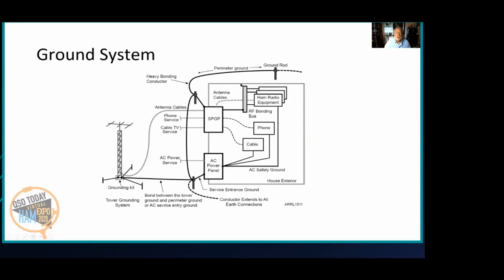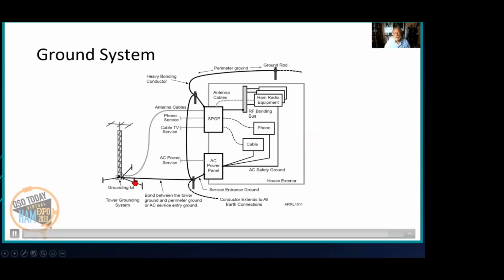Here's your typical station, perimeter ground, heavy wire outside. Every external earth connection is bonded together. Your tower is grounded. It's bonded to the perimeter ground system. If it's more than 50 feet from your station, this becomes less effective, but it doesn't hurt anything. The military grounds everything up to 200 feet away from the station, but we don't have their budget.